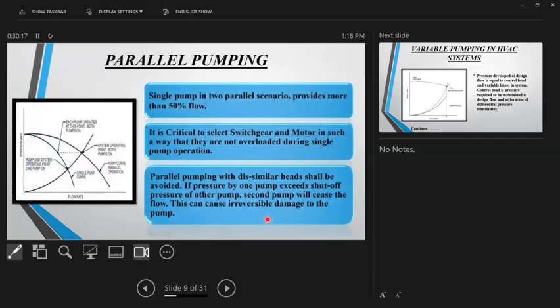And for the next slide, you are mentioning parallel pumping. Say the project has been designed with three pumps, with one standby. In this case, two pumps are on duty with VFD operation, and sometimes some logic has been implemented. So what happens to the flow? Will it vary, will we be achieving the design flow, or are we compromising on the temperature, or on the head you mentioned?